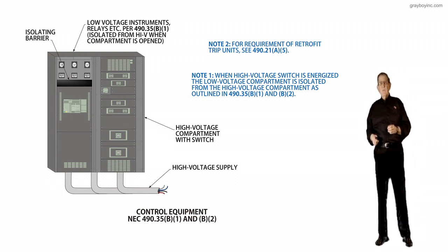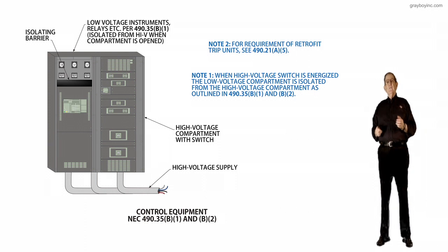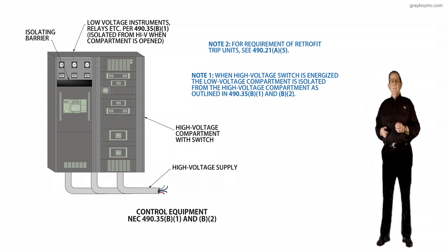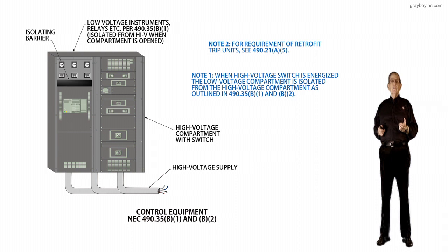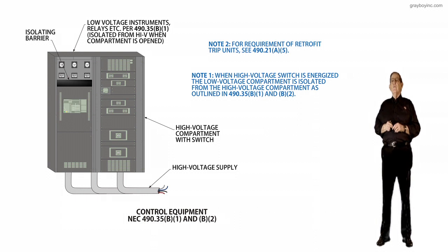Now, first of all, we want to determine the equipment that you see in the illustration. Is it high voltage or low voltage? First, when we look at it, the high voltage compartment with a switch. So we do have high voltage there. And then if we go up to the second callout, that I call the isolation barrier, you see there. And then the third thing, you have your low voltage instruments, relays, and so forth.